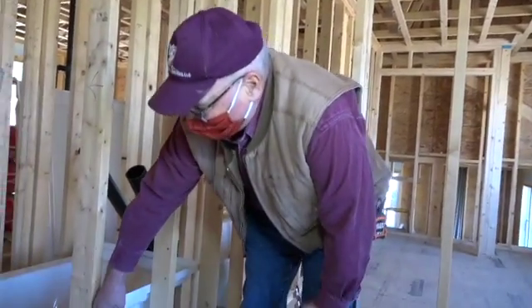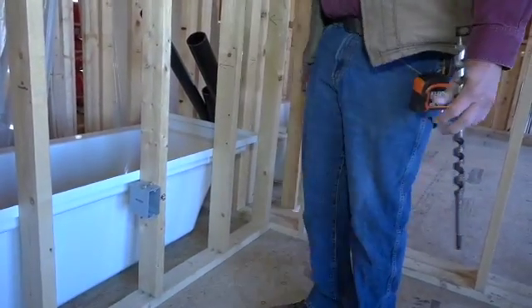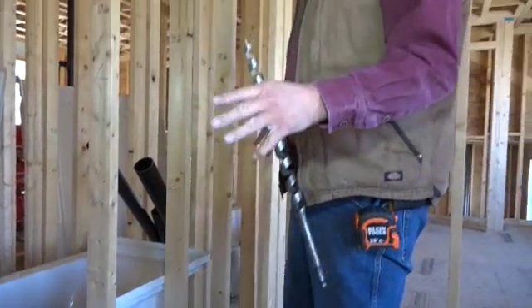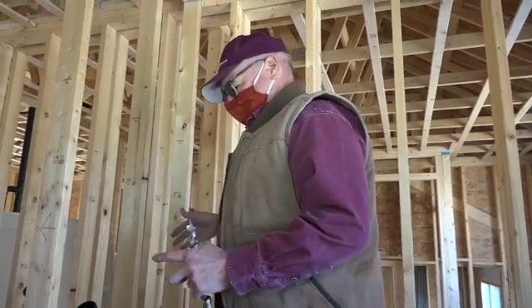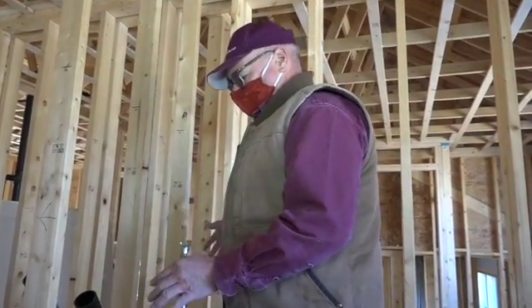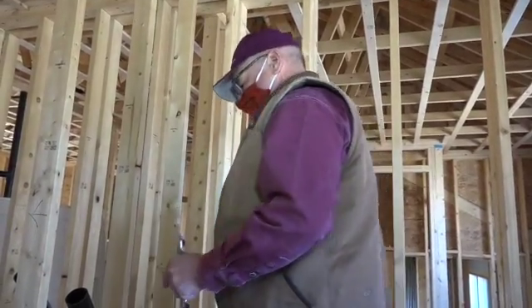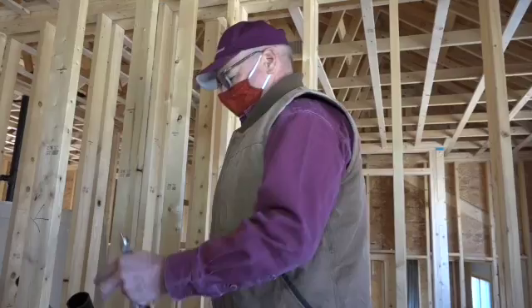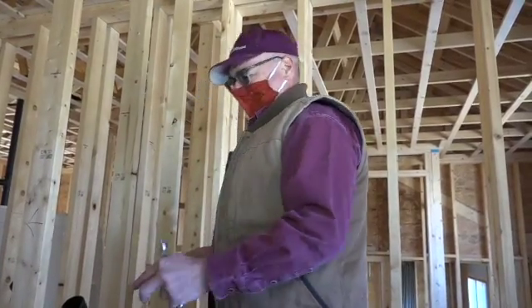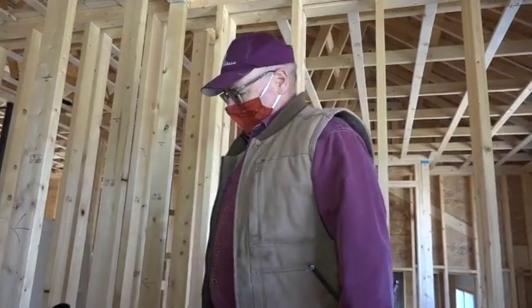Okay, these are receptacle boxes. In a residential home, there's a requirement that no point along a wall be further than 6 feet from a receptacle box. That means every 12 feet you have to have a receptacle box, or if there's a 2-foot wall, you have to have a receptacle box. That's so lamps, which all have 6-foot cords, don't need extension cords, which are dangerous.